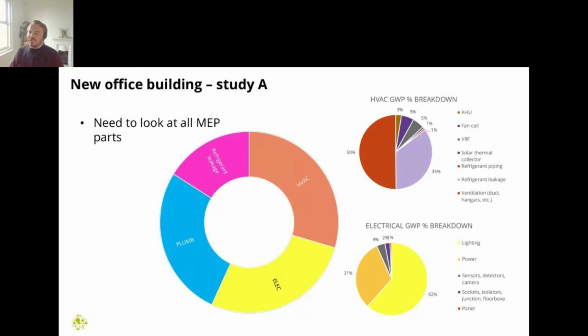One key parameter we identified on the heating and cooling side was the impact of refrigerant leakage. That's really important because with non-combustion solutions now being the primary approach within buildings, we're looking at the design of air source heat pumps, potentially VRF systems, and ground source heat pumps. Anything involving a refrigerant, we need to know exactly what it is, what the charge is, what the leakage rate is, and make good decisions with understanding of the potential embodied carbon impact. This is one of the key topics we continue to research and develop internally, both in the UK and globally.